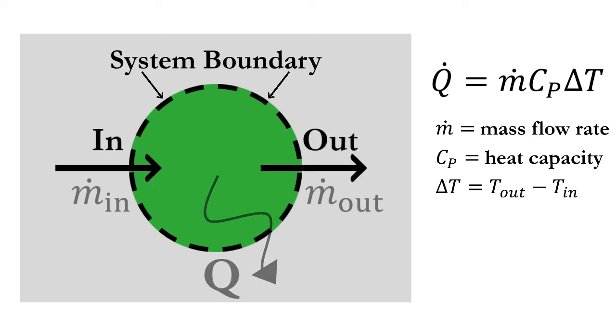Finally, we have to determine which fluid temperatures are needed to determine the heat duty. The temperature change used in the heat duty equation is the difference between the inlet and outlet temperature of the hot or cold fluid. That means we should choose a system and a system boundary that allows us to determine this temperature change.